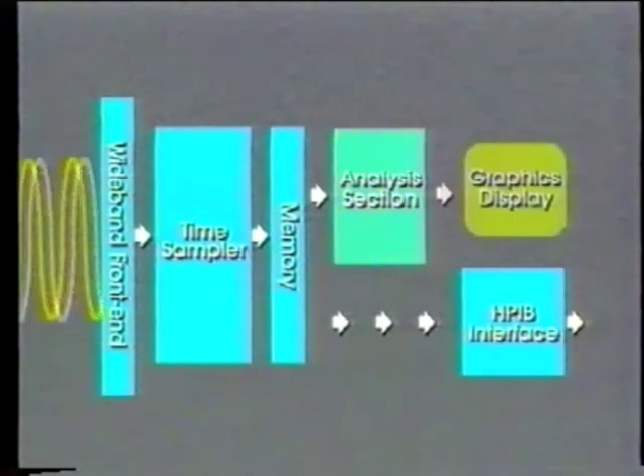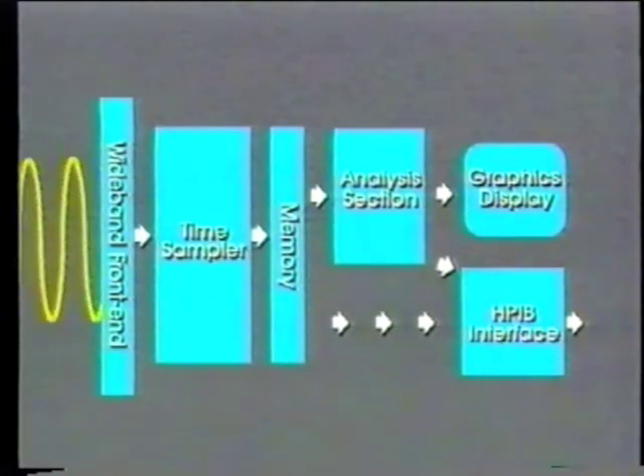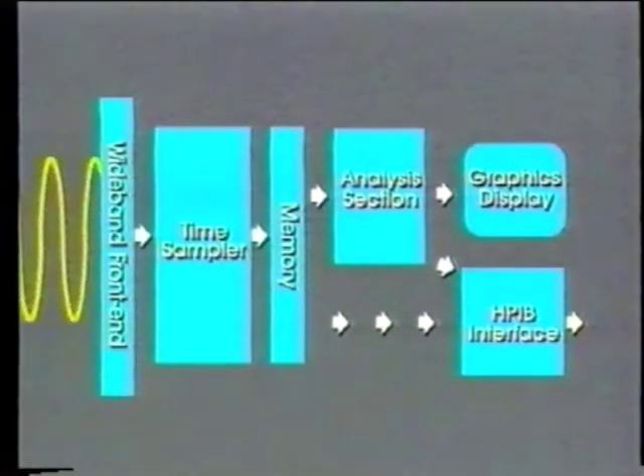From here, the raw binary data takes one of two routes. It can be sent through the HPIB interface for analysis by an outside computer, or it is sent to the analysis section of the 5371A. Results are then shown graphically on the display screen, or sent in floating point or ASCII format through the HPIB interface to an outside computer.